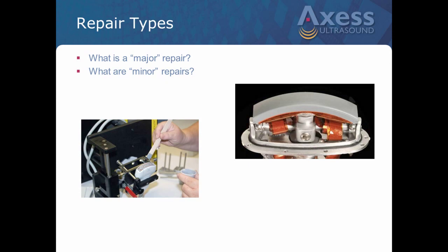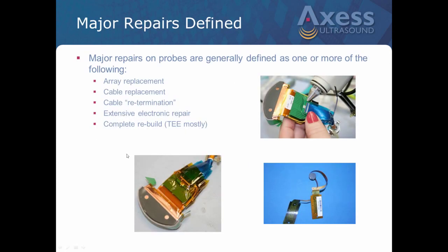Cable replacements on major repairs, just again, just sharing, this would be an entire replacement and what those look like. Terminating the array, I mentioned that. If you look at this, most of the arrays have some sort of flex circuit, and then we have to solder these individual coax wires on here. And these do run from about a 40 gauge upwards to even 48 gauge wire. So it's tiny, tiny wires with a center conductor and a ground shield and an outer jacket. So it's not something that you can just whip out your trusty soldering iron and do. So, some close-ups of that.